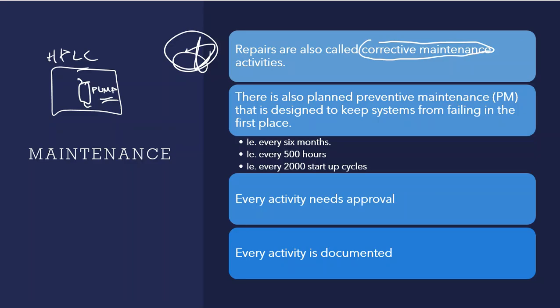Preventive maintenance is the idea, abbreviated as PM. So preventive maintenance means going in and seeing that there are pieces that will wear out, and we replace them before they give you a problem - we are preventing a problem from happening, we hope. So on a routine basis, maybe every 3 months, every 6 months, every year, on an HPLC instrument for example, I'm going to have someone come in - maybe that person's me - and go in and change the O-rings, because they're probably going to dry rot over time.